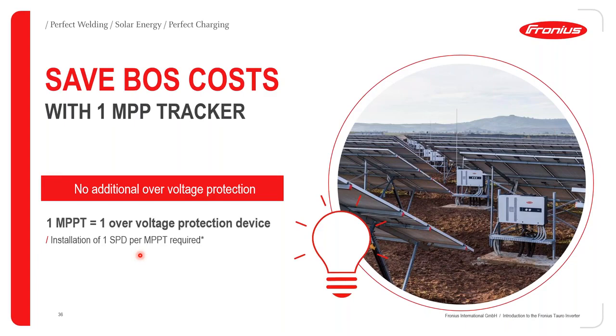A ground mount system would be more ideal when you think about an inverter with only one MPPT, because the solar irradiation will be uniform throughout the day if the panels are facing the same direction or orientation. For a roof mount system, you might want to consider an inverter with 1, 2 or 3 MPPTs, depending on the complexity of the roof structure. The roof structure might not allow uniform distribution of solar irradiation throughout the day, and therefore you might require an inverter that can handle those kinds of variations.